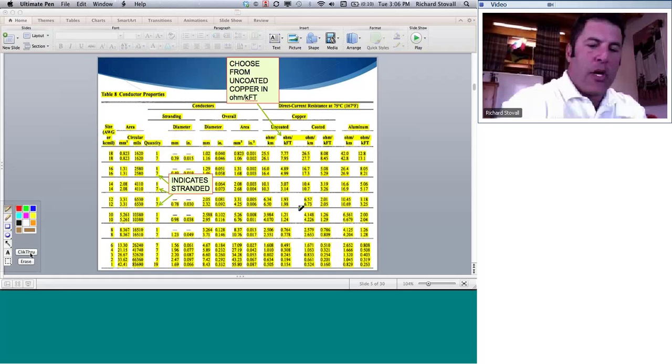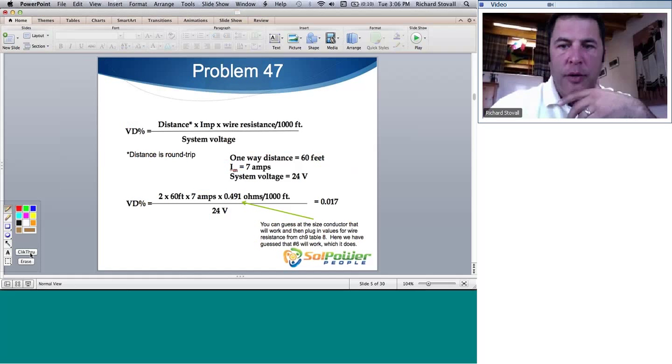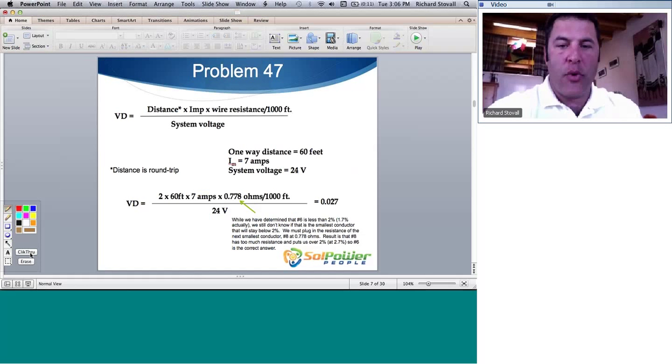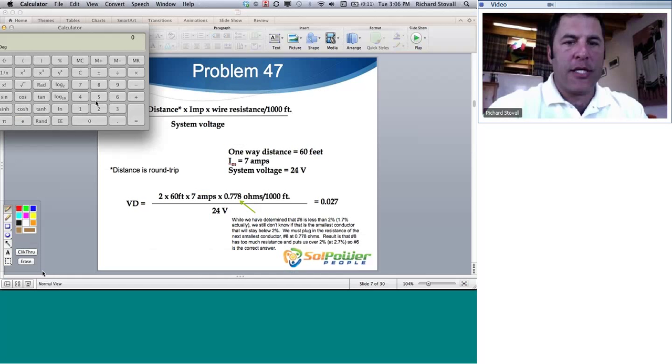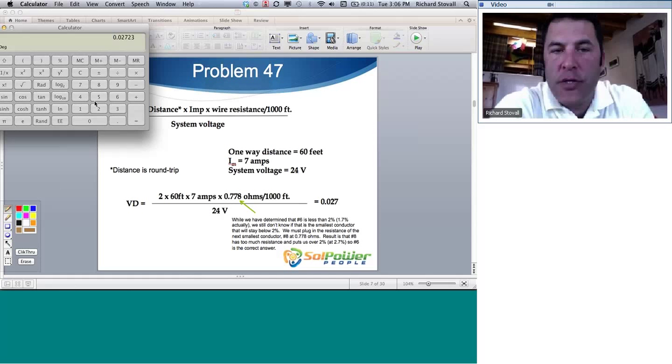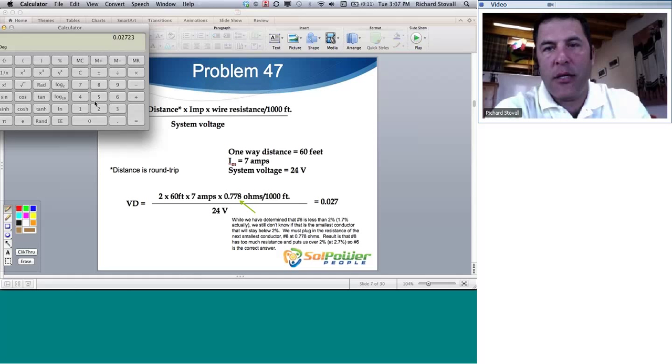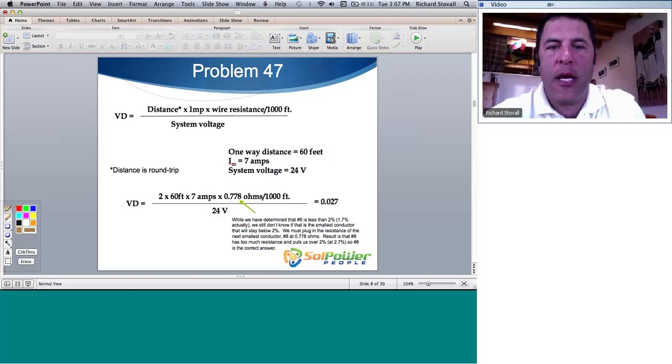Okay, so going back to our PowerPoint. Moving forward, in this case, we're plugging in 0.778 to the same calculation. So we have 2 × 60 × 7 × 0.778 divided by 1,000, and then divided again by 24 volts. And what we get is 0.02723, which is 2.7%, which is more than 2%, so we know that won't work. So therefore, the smallest conductor size that will work is actually number 6 stranded, okay? So that's the answer, number 6, which I believe was...